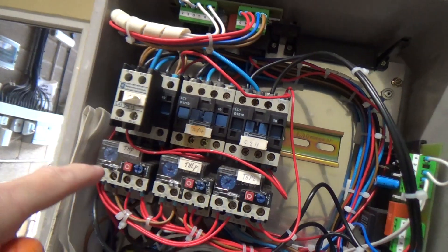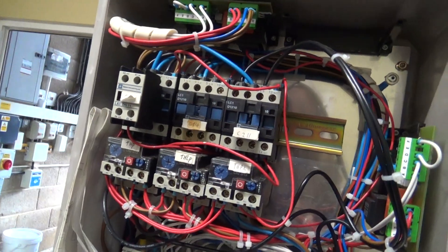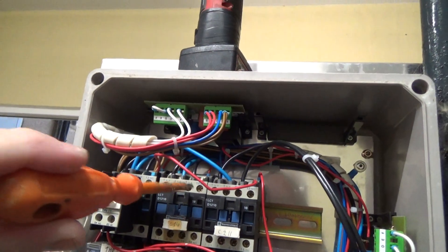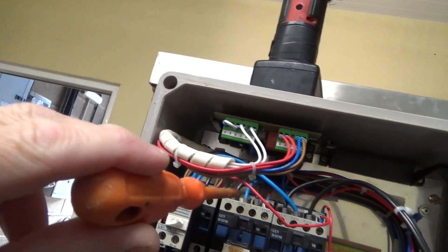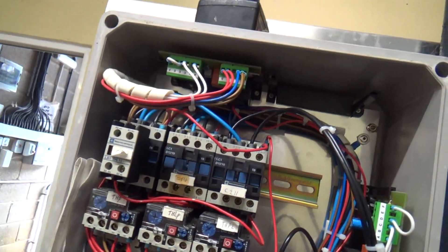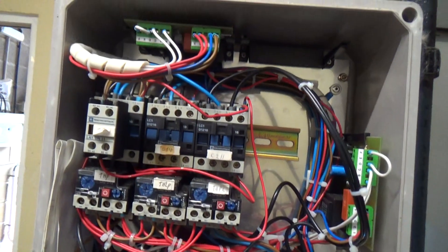THP, THP2 - I think it's pump one and pump two. LP - I think it's a blow-up? I don't know without looking it up in the book. So we'll get a test meter and we'll see if we've got power coming in, and then we'll see if we've got power on the coil. Maybe the coil's gone. There's a definite smell of burning in that box.